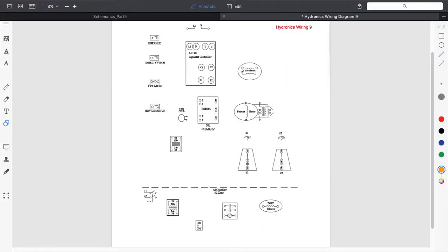In this video, we're going to be talking about Hydronics wiring diagram number 9. Okay, now this diagram is actually a pretty interesting diagram because we have a two-zone hydronic system with a singular circulator. We have an oil burner, and we also have an air handler that's on zone 2. So all of this has to be tied in together.